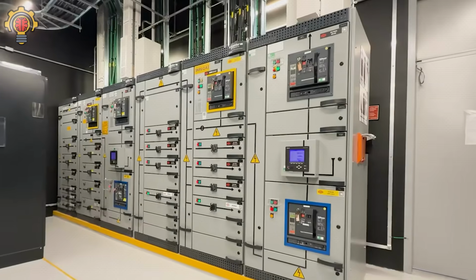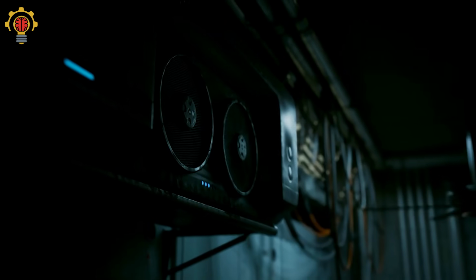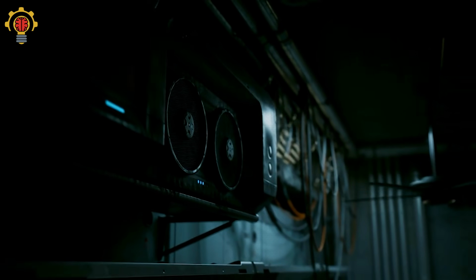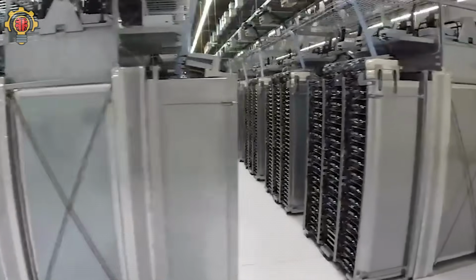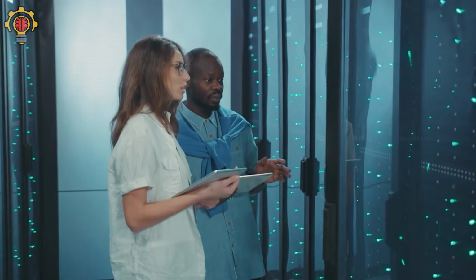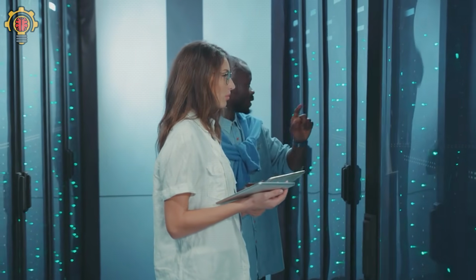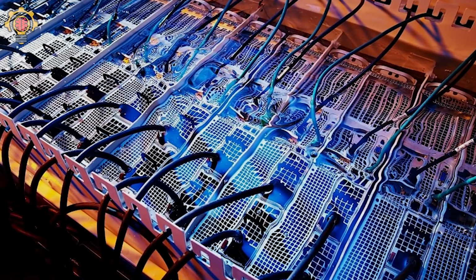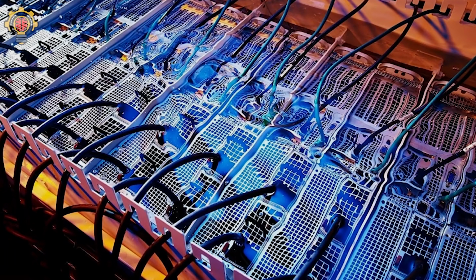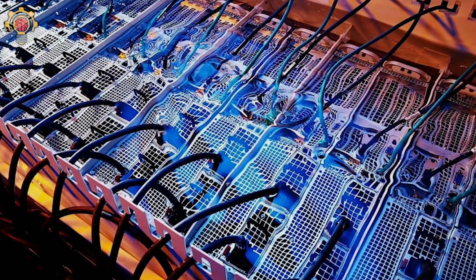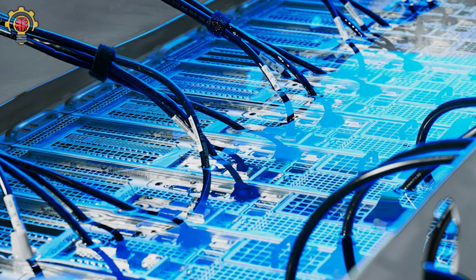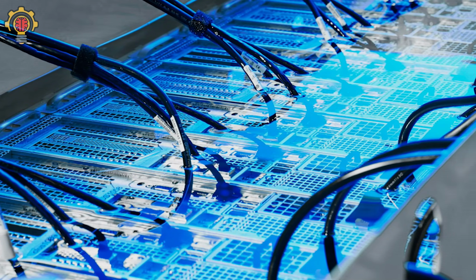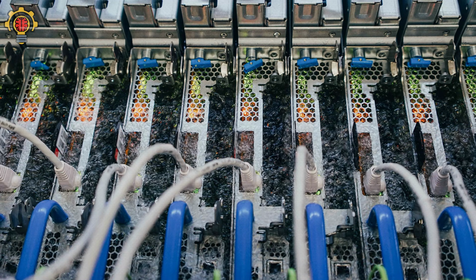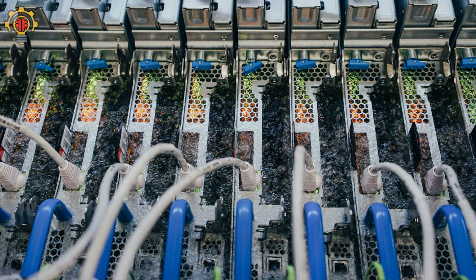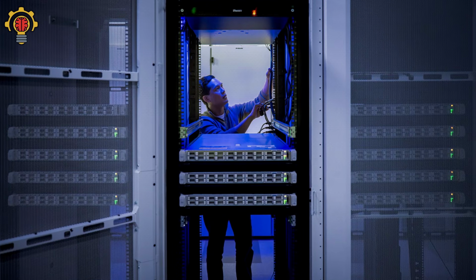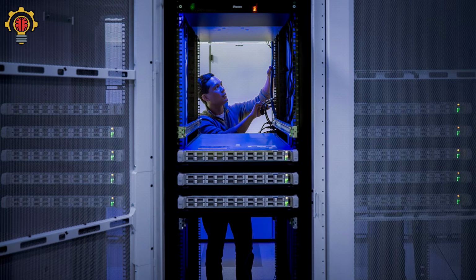Some systems use liquid-cooled heat exchangers built directly into the rack. Small fans move hot air across cooling coils filled with cold liquid, removing heat almost instantly. Other designs place heat exchangers directly on the rear doors of the racks, capturing heat the moment it exits the servers. And then there are immersion cooling systems. Entire servers are submerged inside special non-conductive liquids designed specifically to absorb heat. No traditional airflow, no massive fans, just direct thermal transfer into engineered cooling fluids. It sounds futuristic, but many companies are already investing heavily into this technology, because the future of computing is producing more heat than traditional cooling systems were ever designed to handle.